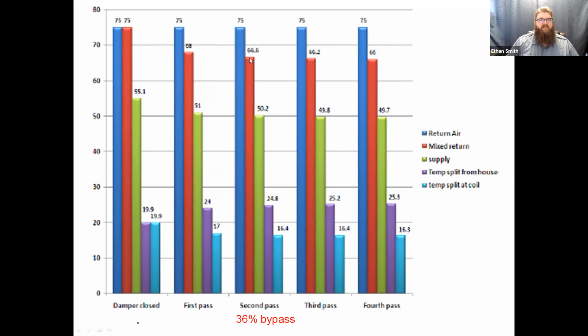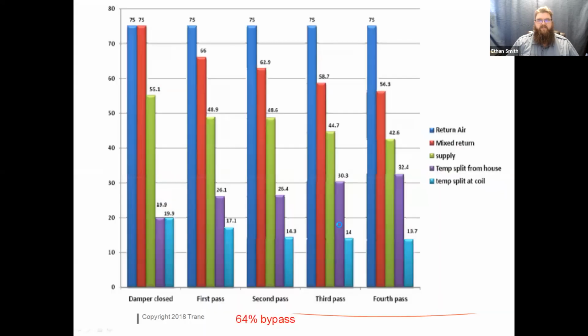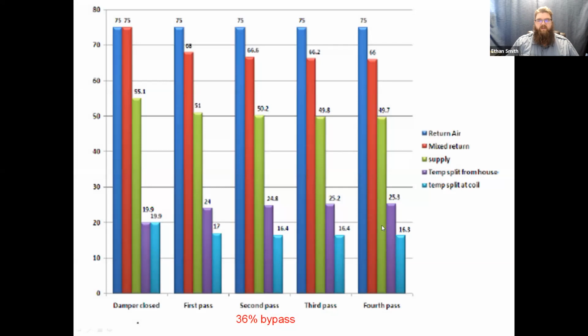Second pass, we're even lower on our return and even lower on our supply. My temp split at the coil just keeps dropping, guys. This is the smoking gun here, though. This temperature split at the coil keeps dropping on us, so this is an indication that we are actually losing capacity out of our indoor coil.